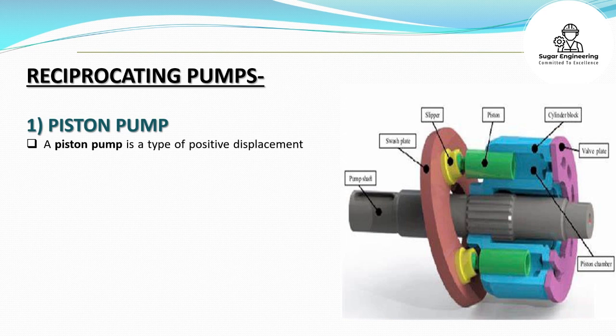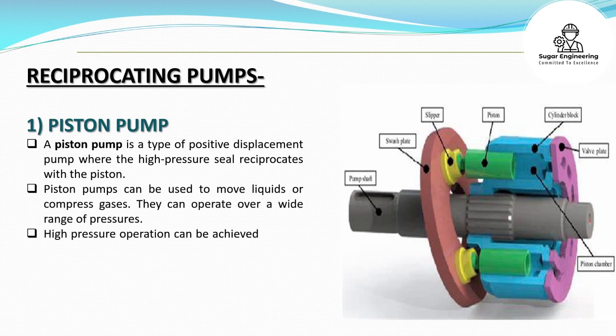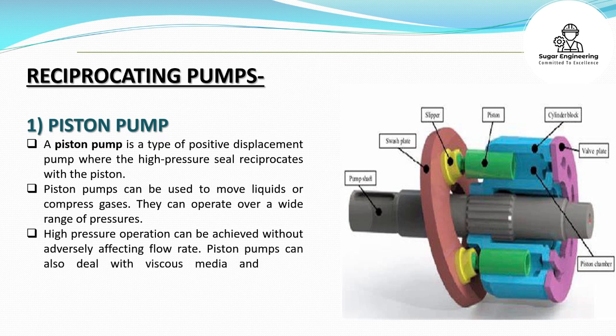Reciprocating Pumps. 1. Piston Pump: A piston pump is a type of positive displacement pump where the high-pressure seal reciprocates with the piston. Piston pumps can be used to move liquids or compress gases. They can operate over a wide range of pressures. High-pressure operation can be achieved without adversely affecting flow rate. Piston pumps can also deal with viscous media and media containing solid particles.